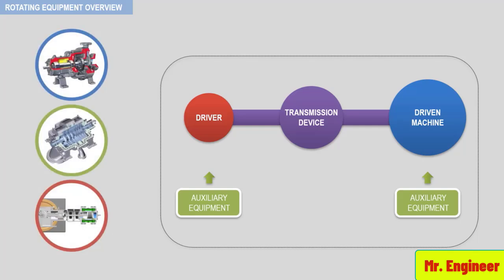The answer is all four. Regardless of the type of unit or train, a driven machine, a driver, a transmission device, and auxiliary systems must always be present. When you are asked to inspect G300 or K100, you are actually inspecting the G300 pump unit or K100 compressor train. Failure to recognize this fact will severely limit your troubleshooting scope and ability.